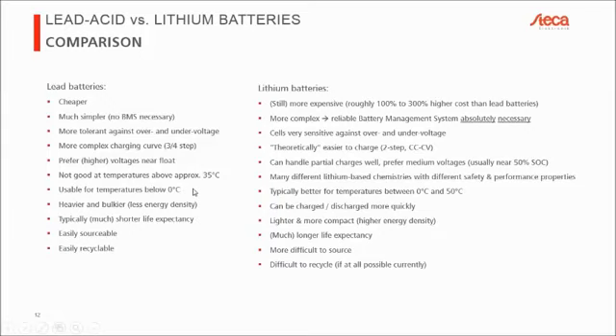Lead batteries are usable below 0 degrees. Lithium batteries typically are not. There are a few exceptions, but the majority of lithium batteries are not allowed to be charged under 0 degrees Celsius. Most of them can still be discharged with a reduced current, but they cannot be charged under 0 degrees Celsius. So it's something to keep in mind.